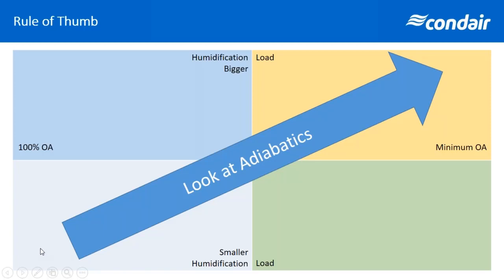Now, if we're accepting that having a properly humidified building is important to your bottom line from what we just saw from Dr. Taylor, and I hope we're all accepting that at this point, then 15, 20 pounds an hour will look down here. If we go higher up on the scale where we have a larger humidification load or less required outdoor air, even if you're using an economizer, that's when we really start to look at a real payback from an evaporative system.